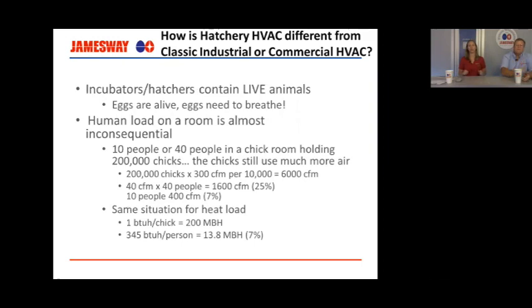So how are we different from industrial HVAC? Basically, the part that's being missed is that incubators and hatchers are containing live animals. The eggs are alive. The eggs are actually breathing, right? They're undergoing an exchange with the environment around them. So they're producing carbon dioxide, and we need to supply oxygen. And like I said, the human load on a room is almost inconsequential. Whether we have 4 people normally working in an incubator room or 6, that's not going to affect the design significantly, because the number of incubators and the amount of air they're using is going to cause more of an effect. And it's the same thing in a chick room.